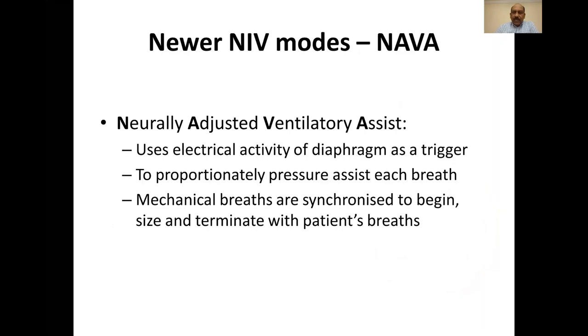I'm also going to briefly mention two relatively new NIV modes. One is called NAVA — Neurally Adjusted Ventilatory Assist — which is probably the most promising and most physiological respiratory mode. Hopefully in the next few years we will hear a lot more about this modality. In NAVA, the electrical activity of the diaphragm is picked up through special electrodes, acting as a trigger to generate pressure from the machine. Each mechanical breath is synchronized in terms of beginning, size, and termination with the patient's effort.